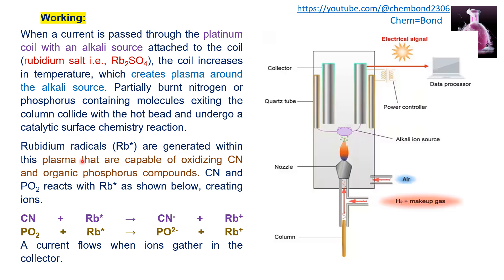What exactly happens near the surface of the bead when organonitrogen or organophosphorus compounds are decomposing is a complex and poorly understood phenomenon. Rubidium radicals are generated within the plasma that are capable of oxidizing carbon-nitrogen and carbon-phosphorus compounds. These rubidium radicals interact with carbon, nitrogen, and phosphorus compounds to produce negative charges and positive rubidium ions. These ions then move towards the collector electrode, producing a current that is amplified and recorded.